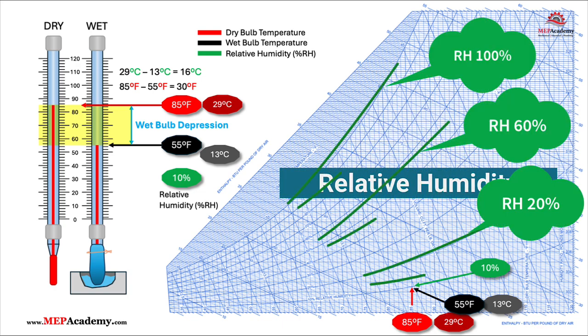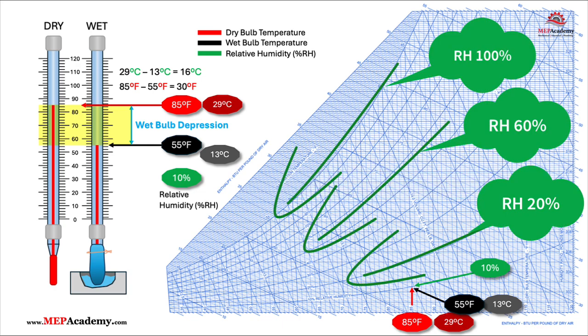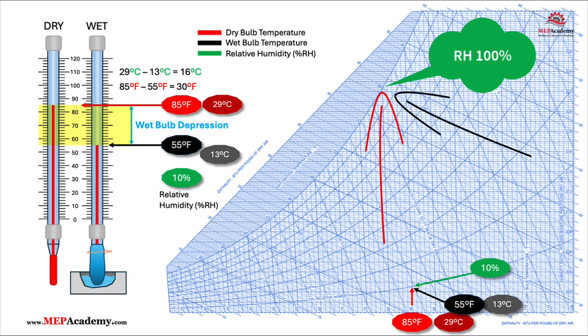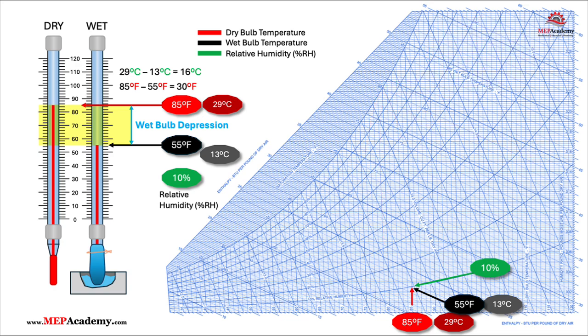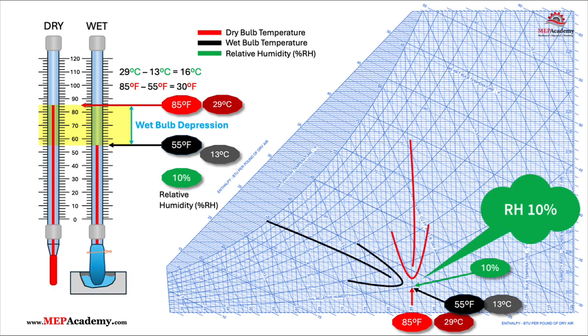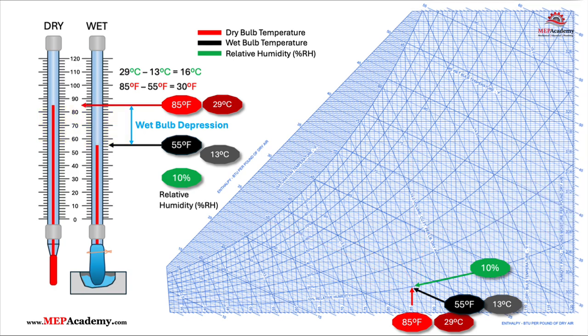Relative humidity is the percentage of moisture the air holds compared to the maximum it can hold at that temperature. When the dry bulb and wet bulb temperatures are close together, relative humidity is high because less evaporation is occurring. When they are far apart, the air is dry and relative humidity is low, as there is more capacity for moisture to evaporate into the air. We can see that the relative humidity is at 10%.